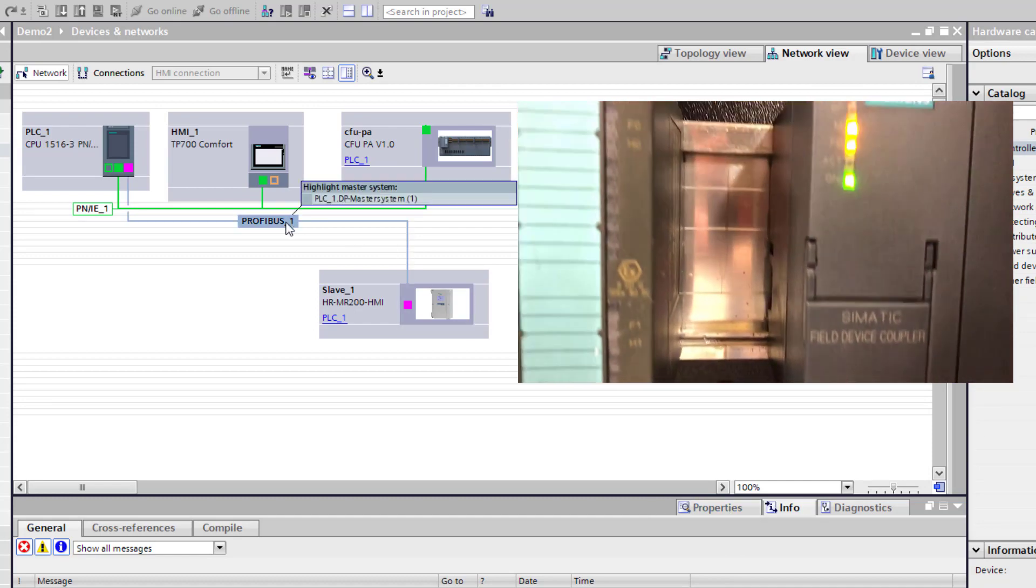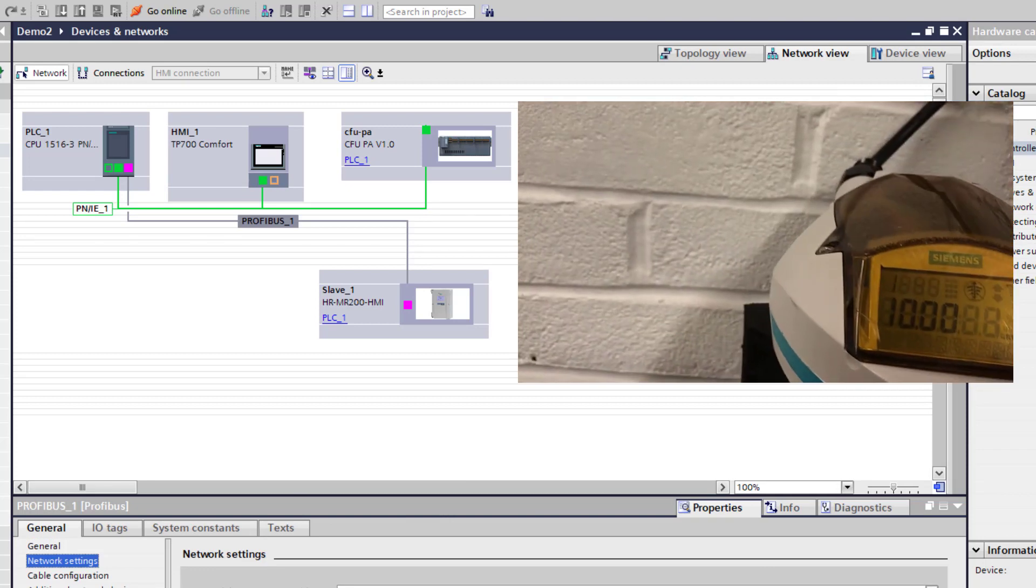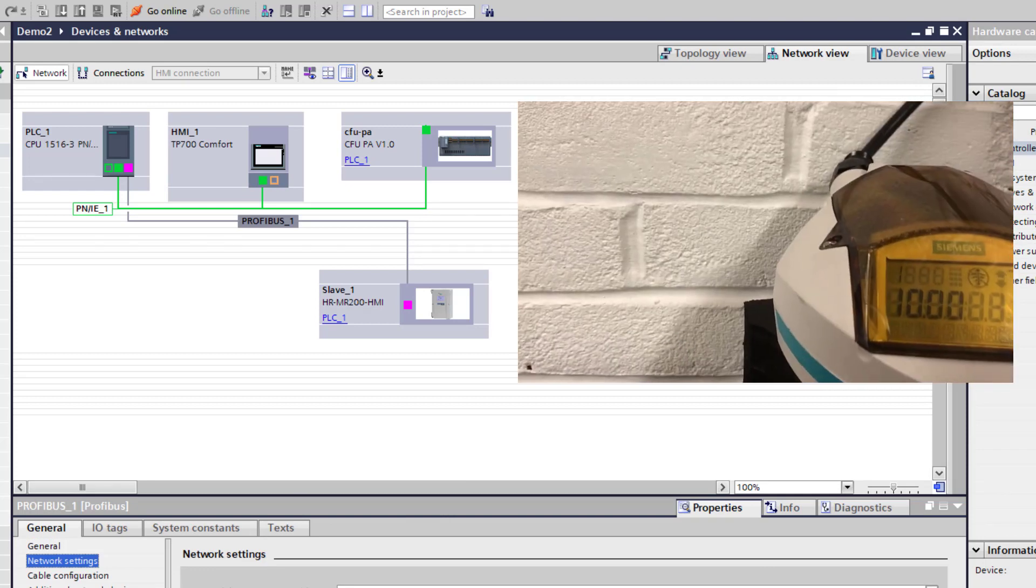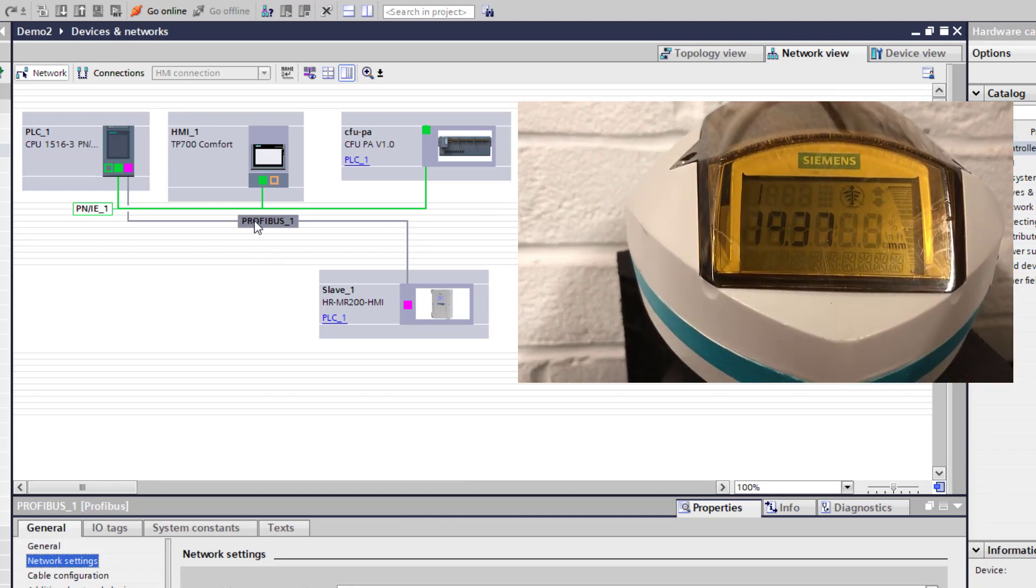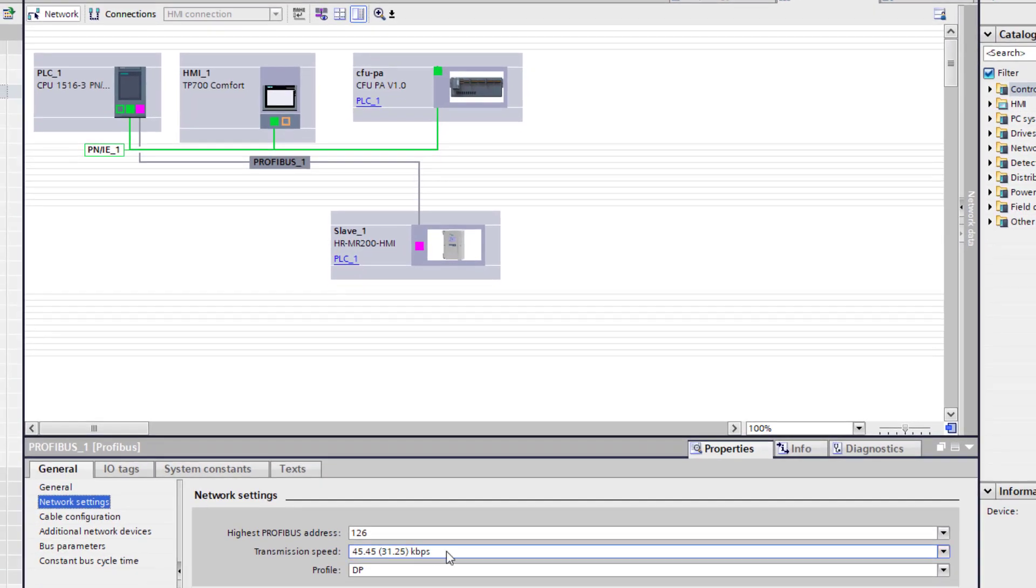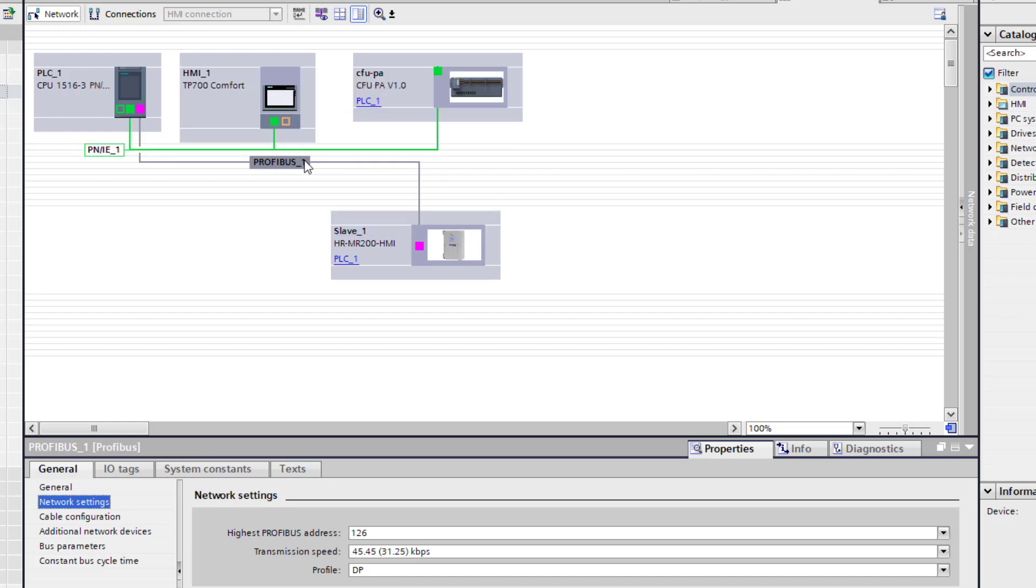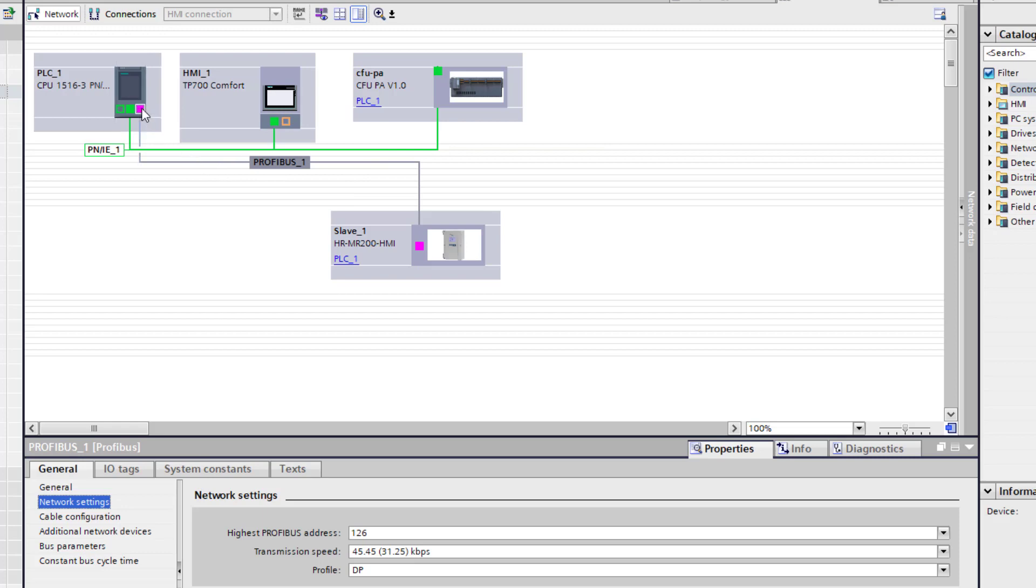Its only weakness really is this: when we add PA devices, we have to slow the bus speed down to the Profibus PA speed. Because we're at that speed, we can use design tools and everything else that I've previously touched on, but we do have to be aware that we are now mixing a DP and PA topology on one cable, and this PLC isn't aware that you're doing that. All it's aware of is that you've slowed down the bus speed.